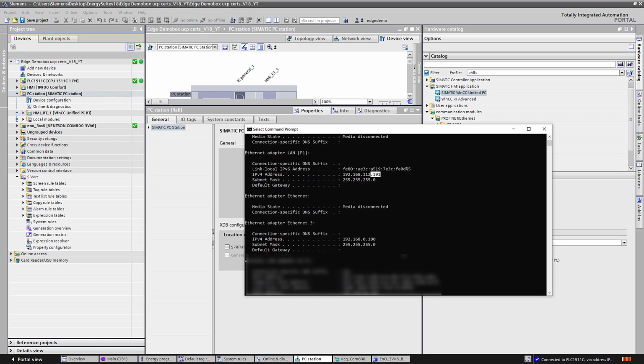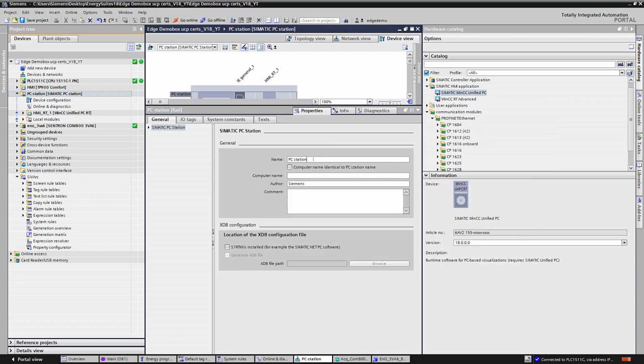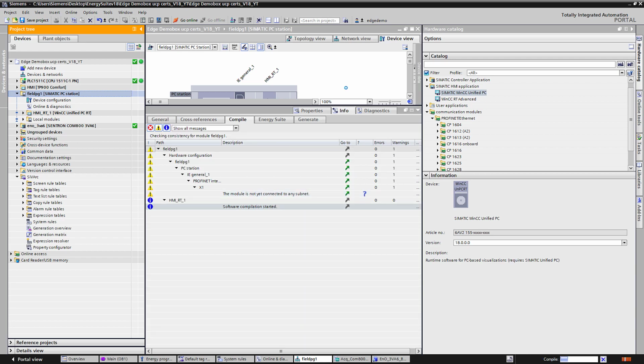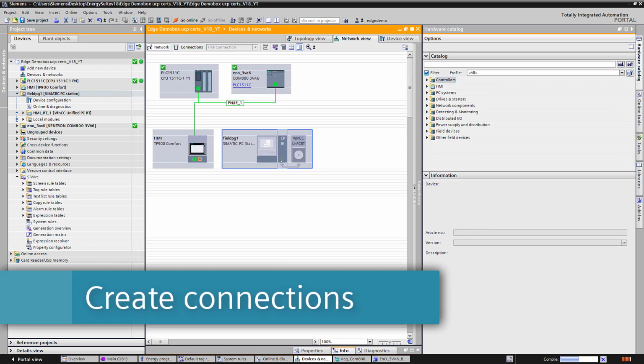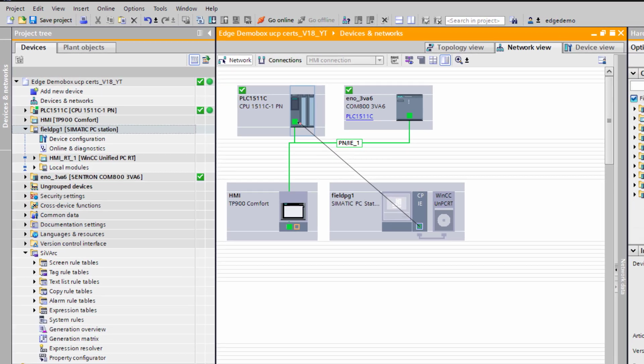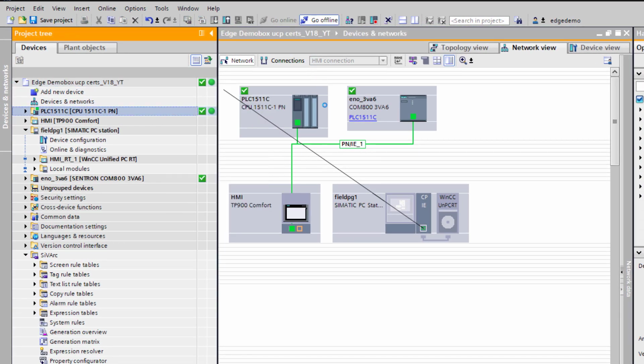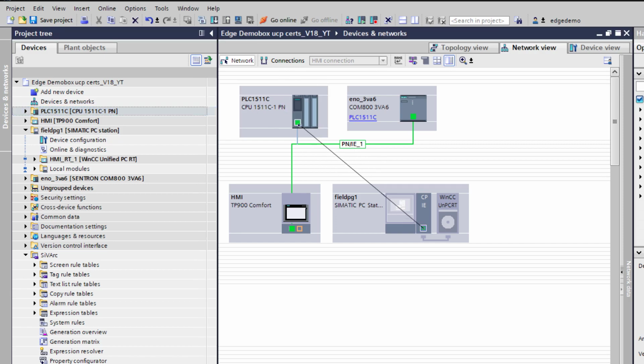And then for the computer name, which really helps resolve better since we are using web-based HMI here, you can see it's called Field PG1. So from there, it's time to attach the module. We'll apply a connection here. It's got to be networked. And in case this ever happens to you, it's good to note you must be offline of the PLC in order to modify a hardware connection. Clicking the Connections option and ensuring you have the HMI connection enabled, drag and drop from the runtime to the PLC.